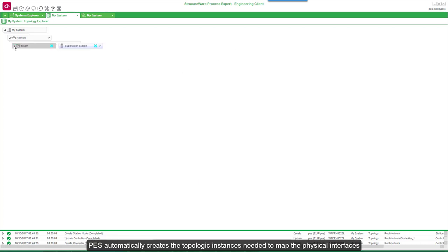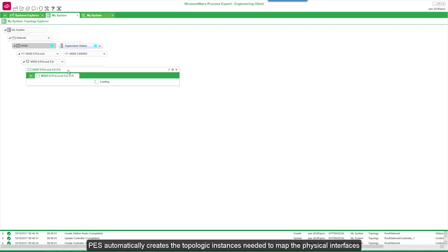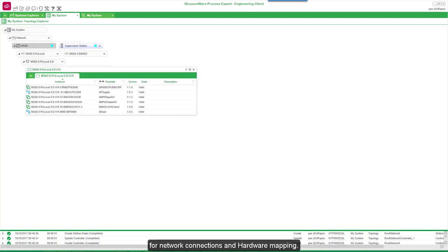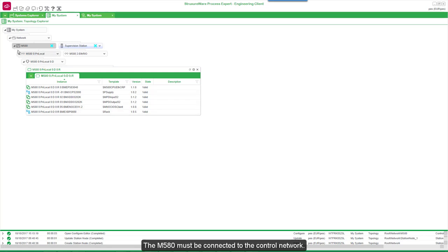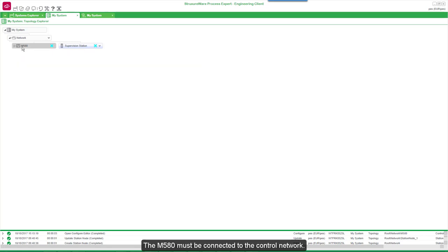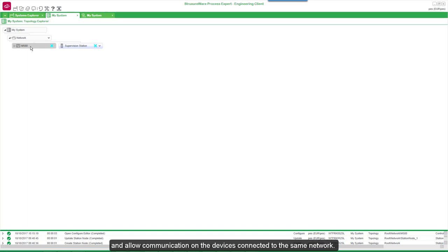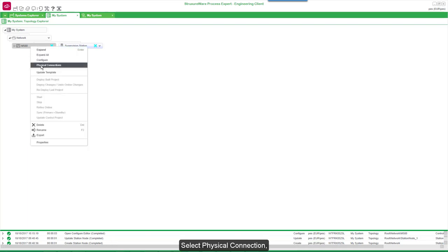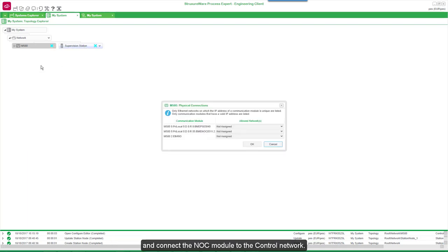PES automatically creates the topologic instances needed to map the physical interfaces for network connections and hardware mapping. The M580 must be connected to the control network. This allows PES to check the IP address parameters and to allow communication only on devices connected to the same network. Select Physical Connection and connect the NOC module to the control network.